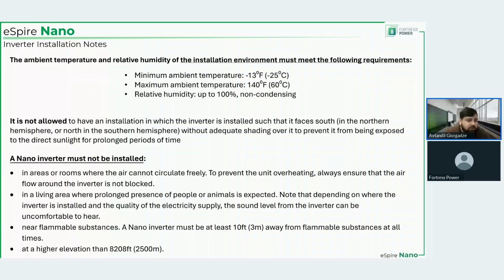I don't know where this webinar finds each and every one of our attendees today, but just a side note, maybe it's useful to mention that in the southern hemisphere, you try to avoid the north-facing wall. And again, that is without the shading. If you have adequate shading, you should be fine. Then, the nano inverter must not be installed in areas or rooms where the air cannot circulate freely because, as I said, this is an air-cooled unit.